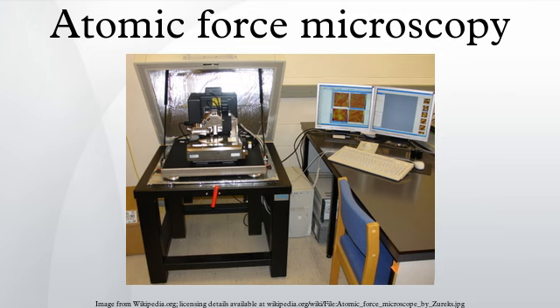Basic principles. The AFM consists of a cantilever with a sharp tip at its end that is used to scan the specimen's surface. The cantilever is typically silicon or silicon nitride with a tip radius of curvature on the order of nanometers. When the tip is brought into proximity of the sample surface, forces between the tip and the sample lead to a deflection of the cantilever according to Hooke's law. Depending on the situation, forces that are measured in AFM include mechanical contact force, van der Waals forces, capillary forces, chemical bonding, electrostatic forces, magnetic forces, Casimir forces, solvation forces, etc.